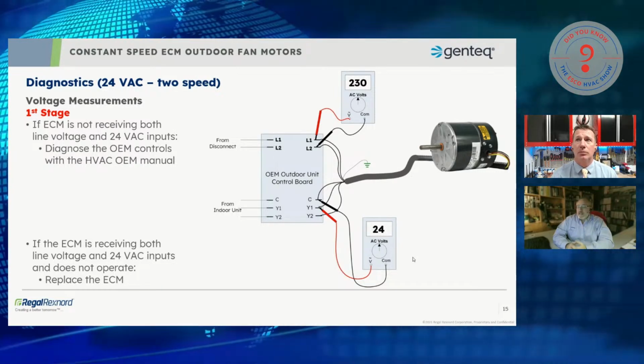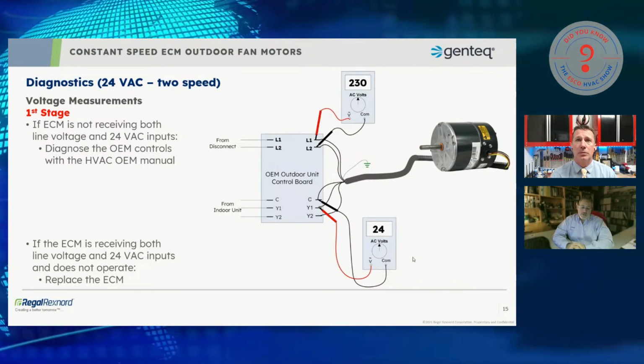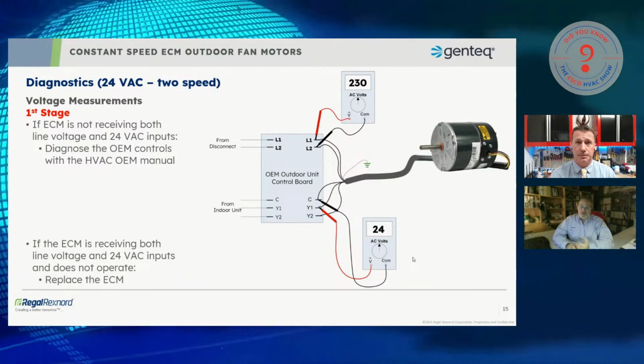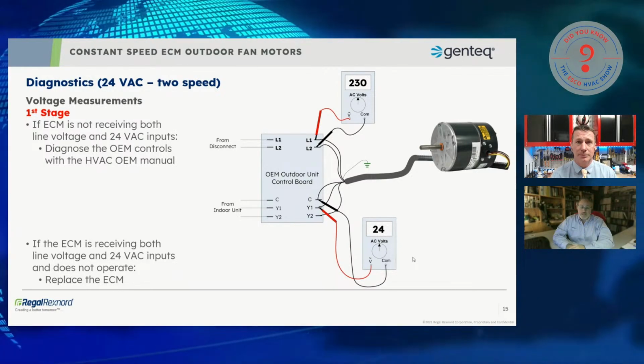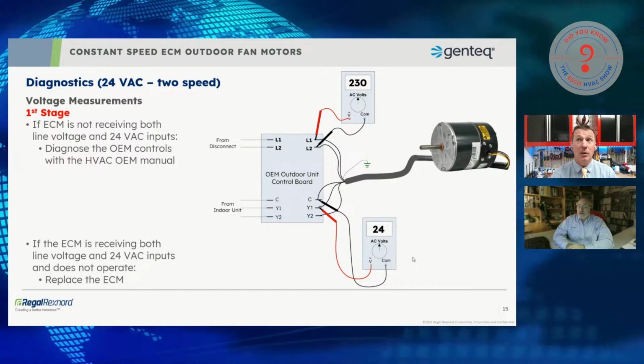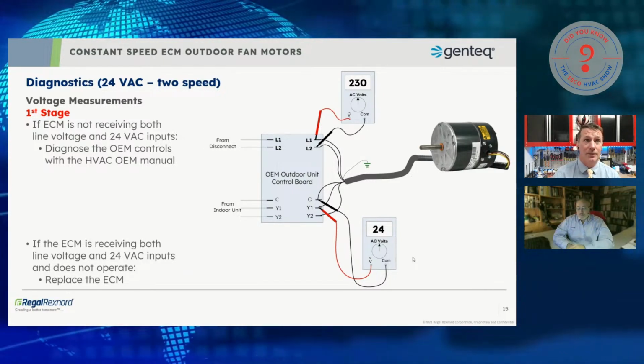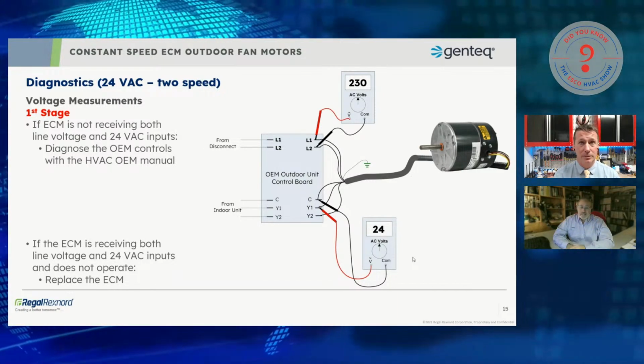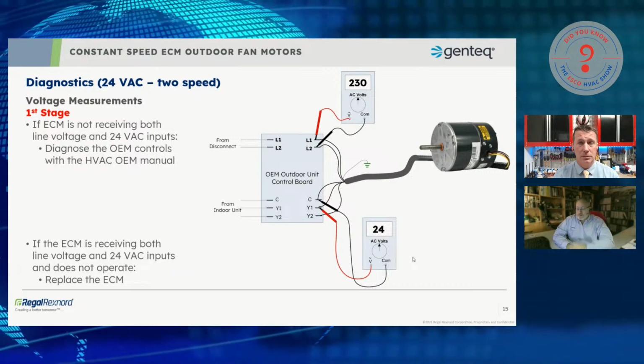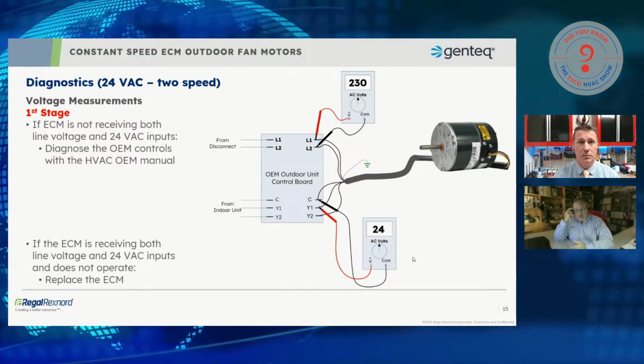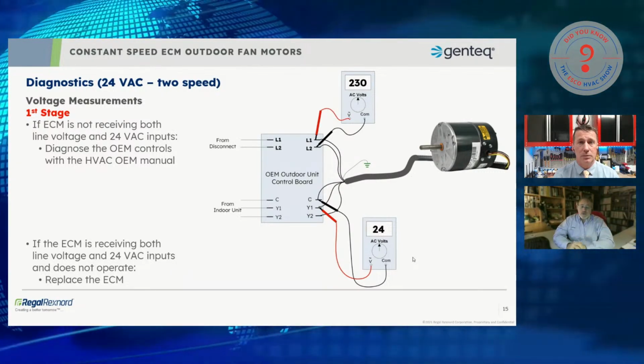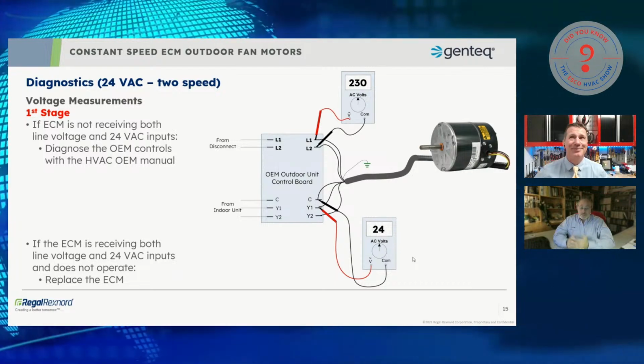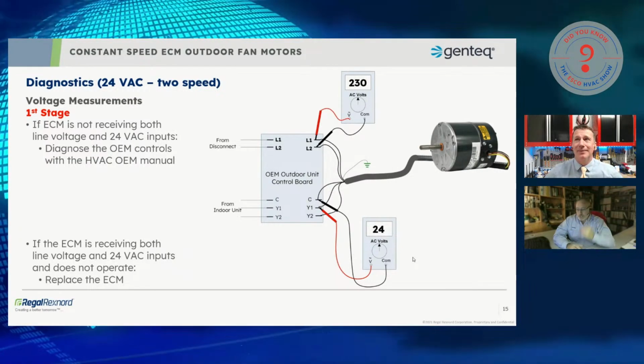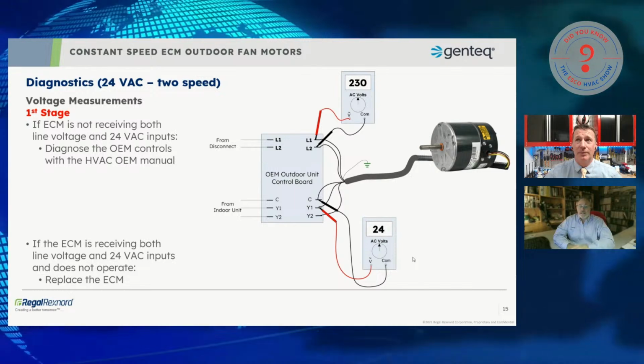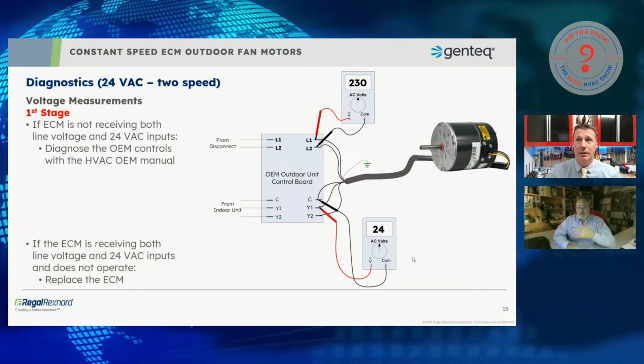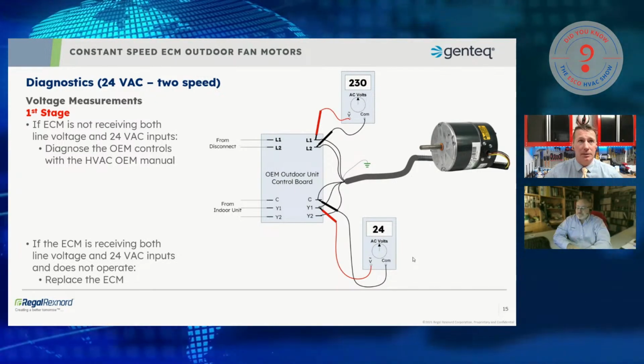Yeah, and I bring that specific scenario up because one of the very few calls I do get on these outdoor fan motors, the technician was having that struggle. It was tripping on high head pressure. It was acting like a dirty coil. It was acting like other refrigeration issues, and so we went through the motor and we found out that the Y2 wire had fallen off. And it was literally just that simple. And the technician just didn't think, since the motor was running, never thought about the fact that it could not be running in its right second speed stage capability. Love it. Great example.